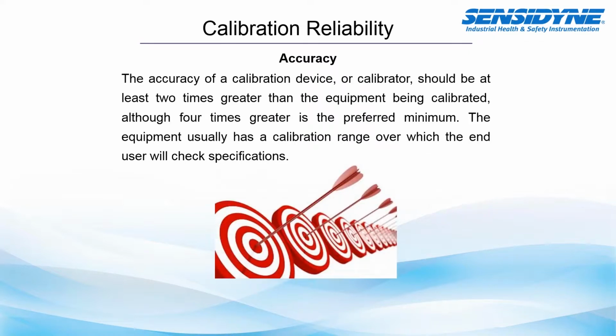The accuracy of a calibration device or calibrator should be at least 2 times greater than the equipment being calibrated, although 4 times greater is the preferred minimum. The equipment usually has a calibration range over which the end user will check the specifications. So when you purchase a calibrator for use, it's important that you make sure that the calibrator's accuracy is at least 2 times the minimum accuracy that you need. And again, 4 times more accurate is preferred.